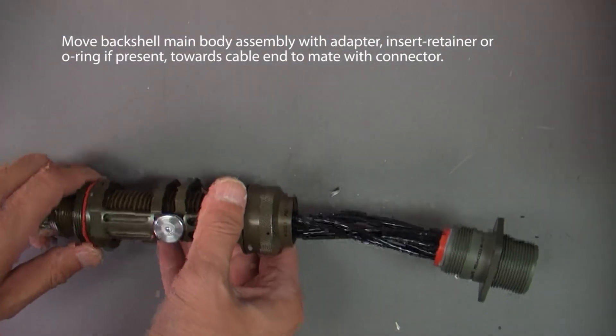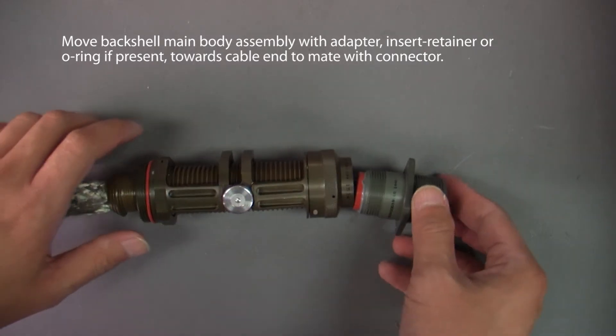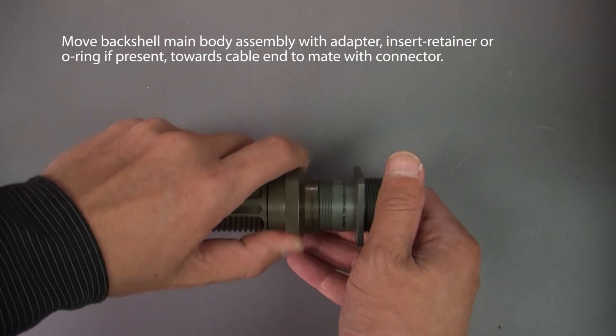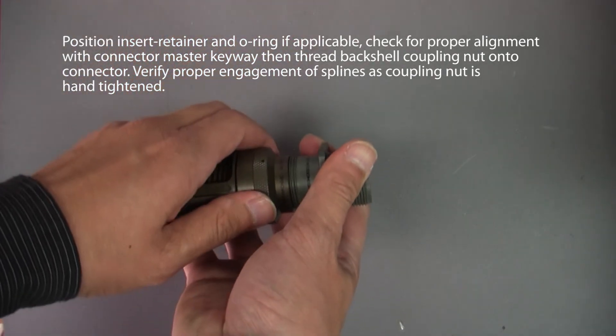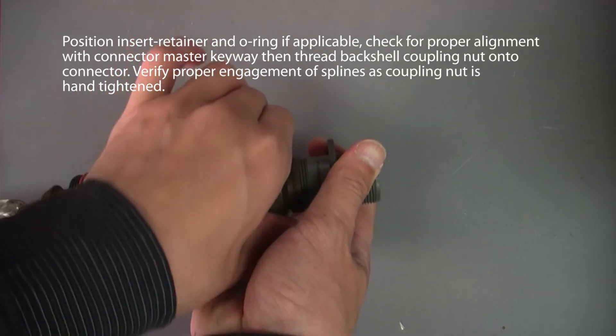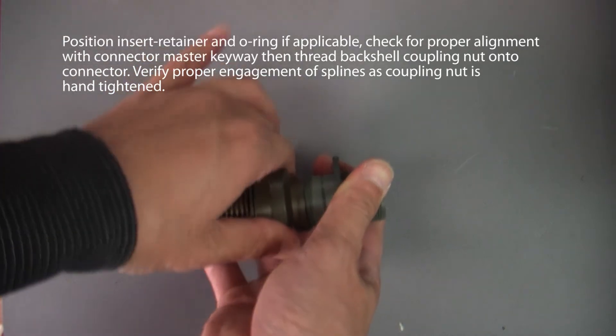Step 6: Attach main body assembly to connector. Move the back shell main body assembly with adapter, insert retainer or O-ring if present, towards the cable end to mate with the connector. Position the insert retainer and O-ring if applicable. Check for proper alignment with connector master keyway, then thread the back shell coupling nut onto the connector. Verify proper engagement of splines as coupling nut is hand tightened.